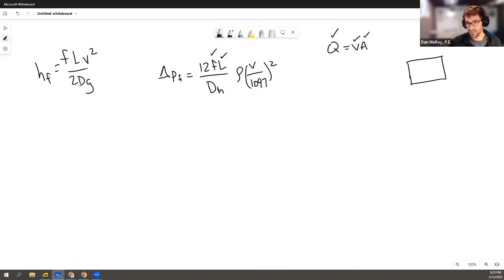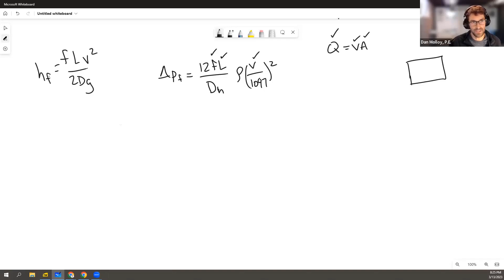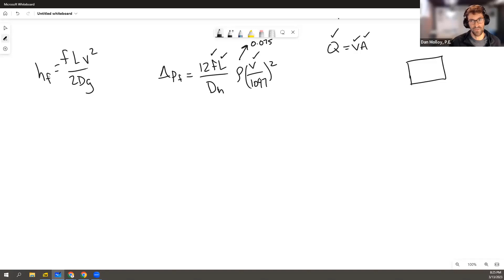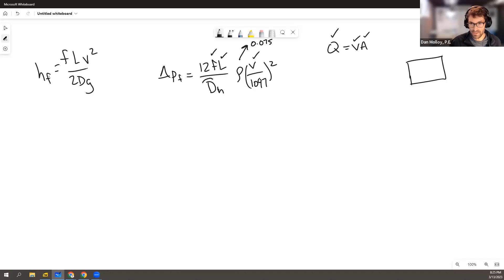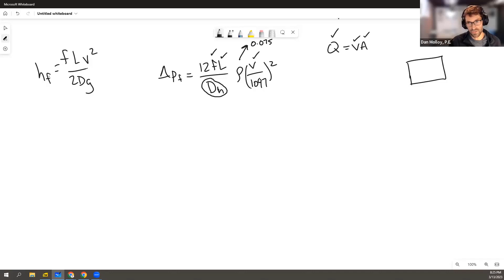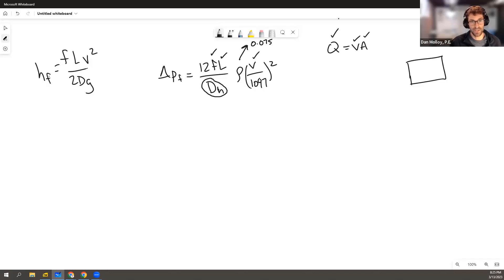So the velocity is knowable. And the density, there's not a lot of information given about temperature, but it's probably like room temperature air. So we're going to make the safe assumption here that the density is just 0.075. That does have to be in pounds per cubic feet. But the most interesting part of the problem is the use of the hydraulic diameter in the denominator. And that's where this solution path tends to go astray from the standard Darcy equation, which would otherwise get you to the same place.